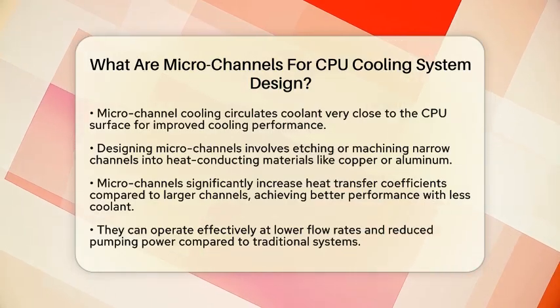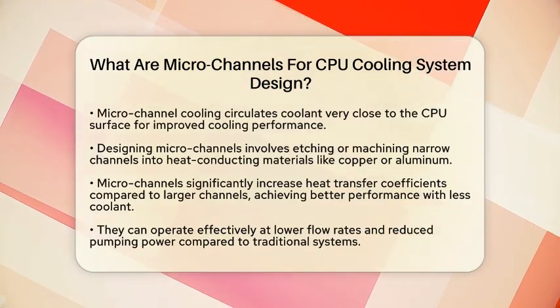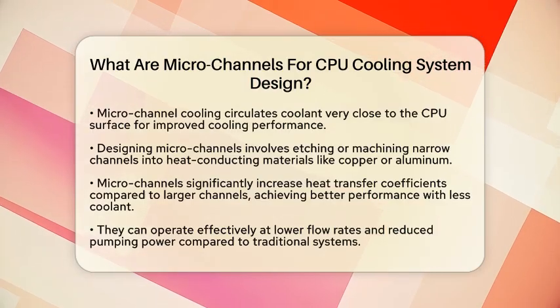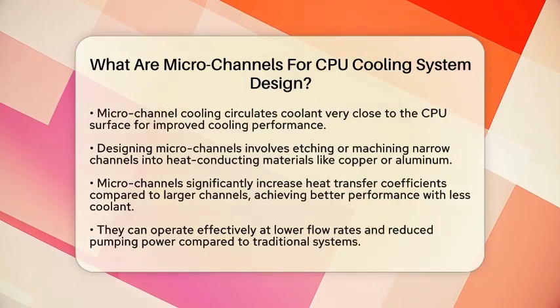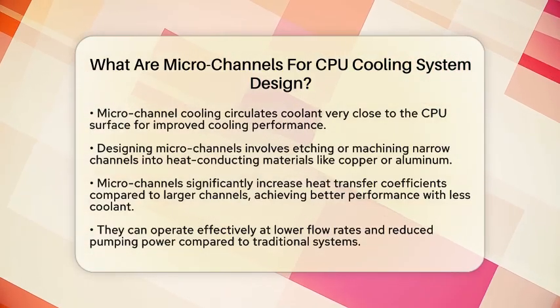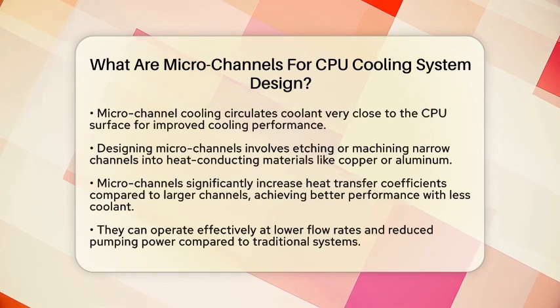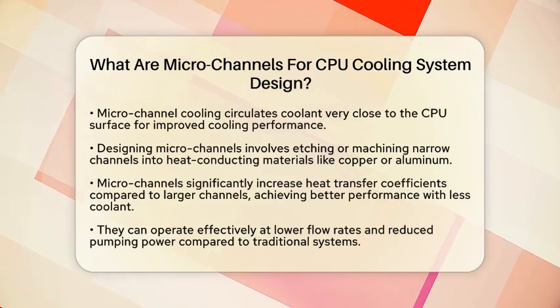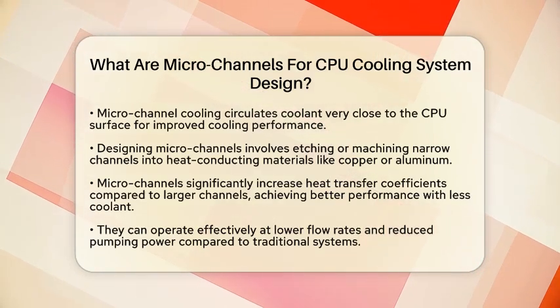This means microchannel coolers can achieve similar or even better cooling performance while using less coolant and requiring less pumping power. For instance, they can perform well at 1/6 the flow rate and 1/4 the pumping power of traditional cooling systems.